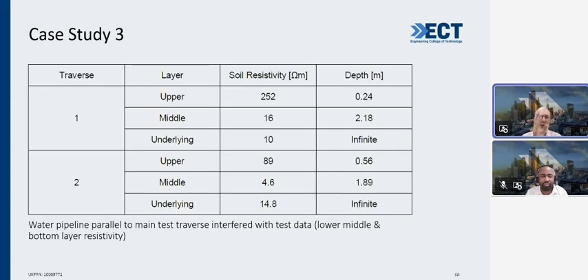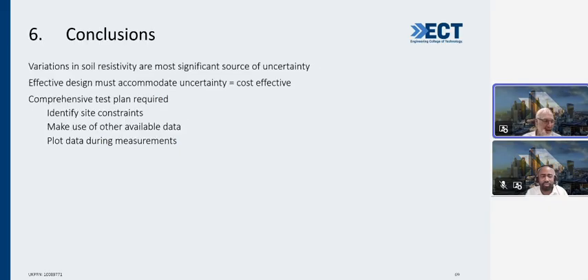Just go back there, go to the conclusion. One other point with the resistivity tests: watch out for installed copper cables or steel cables underground. They may reduce the resistivity, and you've got to be really wary about anything else installed, or there may be an electrical installation nearby which would cause distortions to what you're measuring. So there's a whole art form there. I'm going to do a presentation on resistivity in the next few months, a more detailed one. This is just to give you a few pointers.